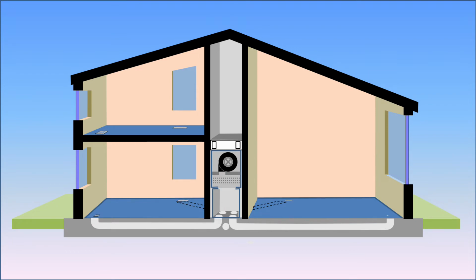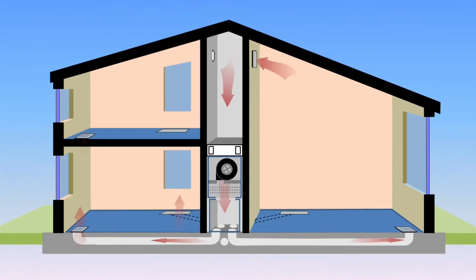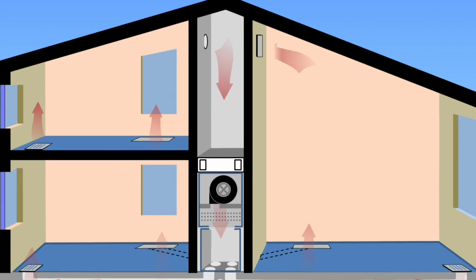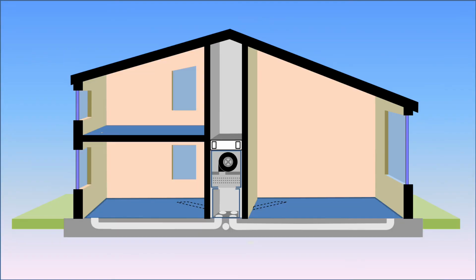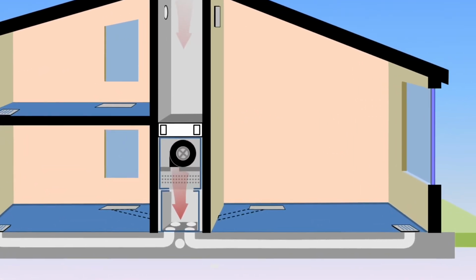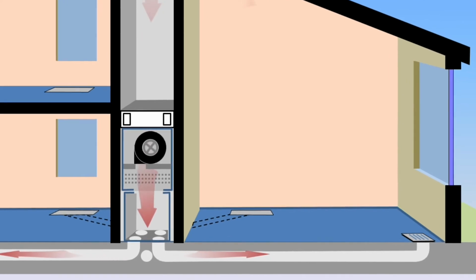To maximize airflow and destratify the air, we need to place the air registers accordingly. To pull the hotter and more humid air off the ceiling, place the return registers high on the wall, near the ceiling, away from vertical and horizontal corners, and towards the middle of the interior wall. To intercept the cold air flowing down from windows and exterior walls, place floor registers under them, about 6 inches off of the wall. This will throw a curtain of upward flowing air to intercept the cold down flowing air.